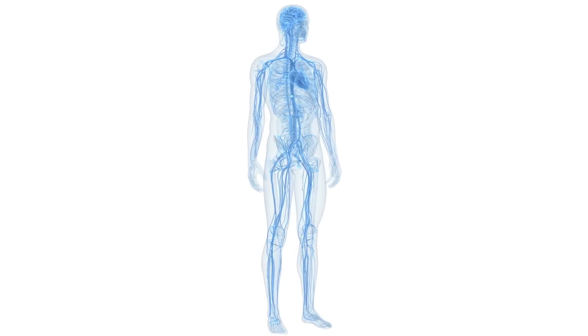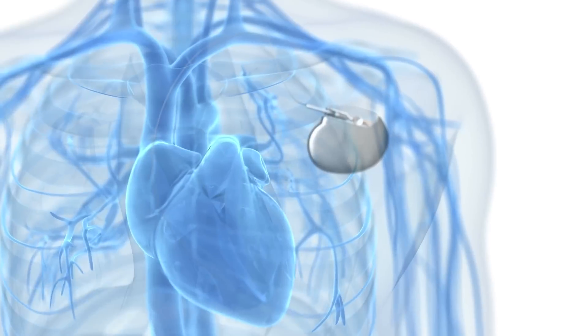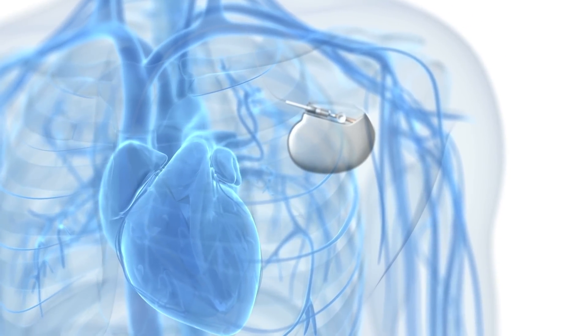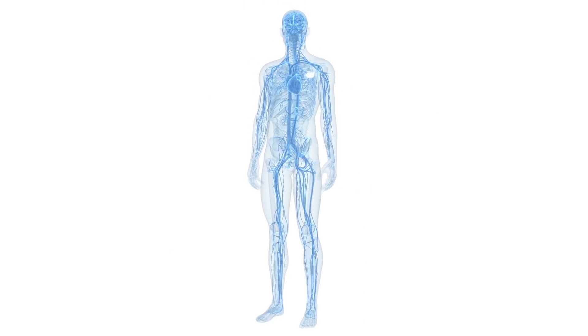To implant medical electronics in the body, they need to be made as small as possible. Most devices are powered by batteries which are very bulky. To eliminate them, inductively coupled coils have been used to wirelessly transfer power. However, the electromagnetic field decays quickly, requiring large receiving coils. Midfield wireless powering overcomes these problems.